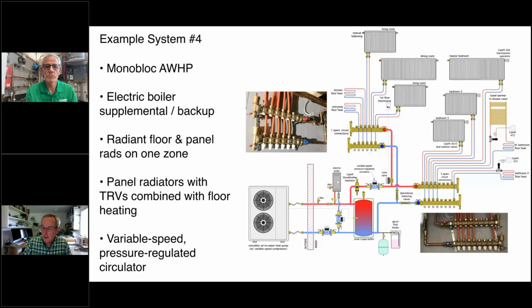And here's what it looks like. We've left some extra connections on the manifold. So if somebody wants to add a towel warmer later on in another bathroom, for example, it's an easy add-on. The system basically uses the air to water heat pump to maintain this tank temperature, and it's got an electric boiler as an auxiliary and supplemental heat source. So a pretty contemporary system.